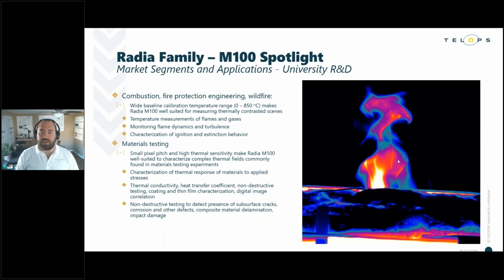So my final application slide here is meant to highlight some of those unique characteristics of the Radia M100 that I mentioned earlier, particularly towards some prominent research areas that we find in universities. So first, M100 is really well suited for measurements in the combustion, fire protection engineering, wildfire research areas, things like that. And that's because the M100 detector has a very high tolerance for saturation, and that's in part due to that restricted spectral band, that 3.6 to 4.2 spectral band that we're using here. So this performance characteristic allows us to offer that baseline calibration from 0 to 850 without using a neutral density filter. It really improves the performance of M100 over scenes that have very strong thermal contrast.